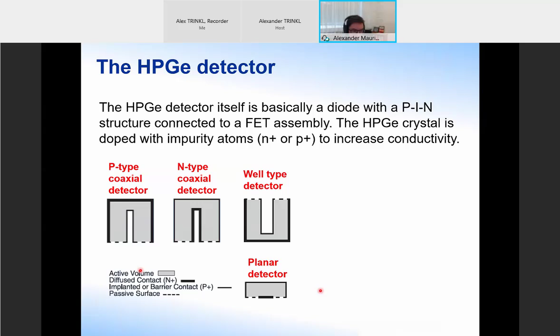There's also some other types of crystals. You might have a well-type detector where you kind of flip the detector on its head almost, not exactly, but almost, and then you can fit your sample here into the well. So you have kind of the detector surrounding the sample, which can be quite nice when you're trying to measure low activities. There's also planar detectors, which have more like a flat, thinner shape, used for low energy applications, for example. And yeah, there are other types as well, but these are maybe some of the more common crystal configurations, with the definitely most common being these coaxial types, p-type or n-type.